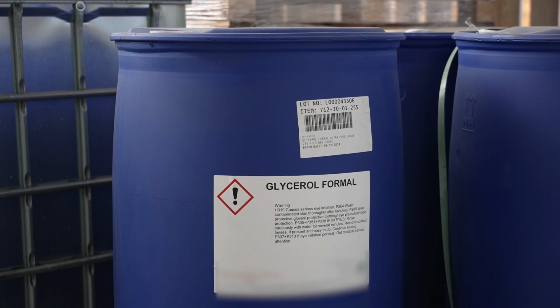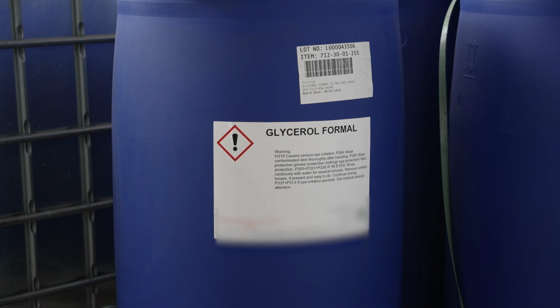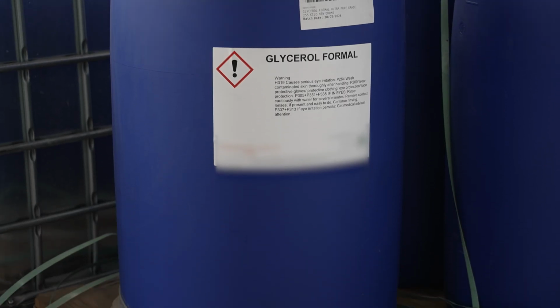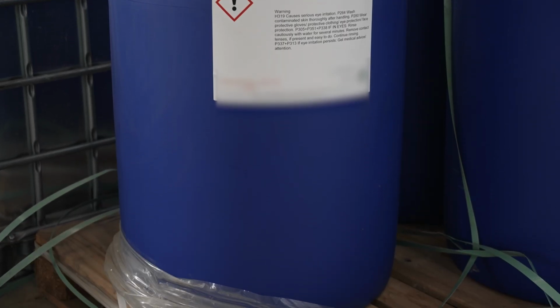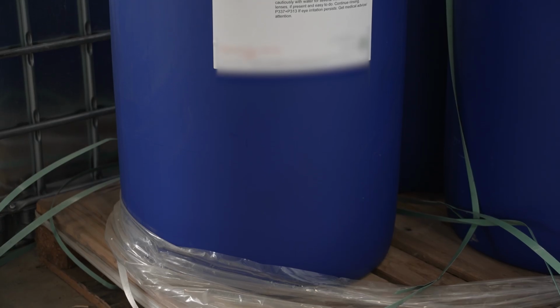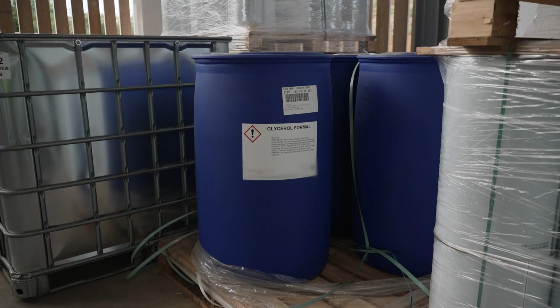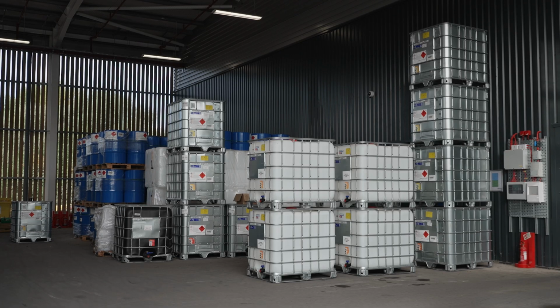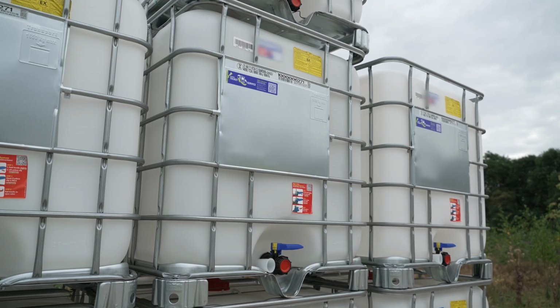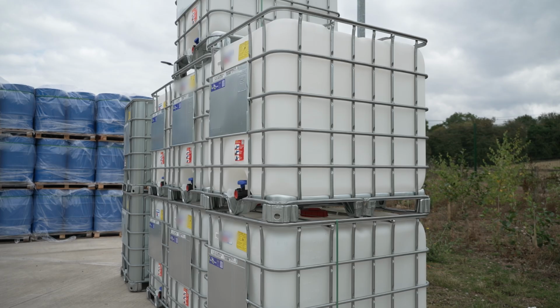Generally, it is recommended that plastic IBCs and drums should not be used for liquids with low flash points, as the plastic surfaces themselves can become charged by brushing against them and any charge buildup in the liquid cannot be removed. Some plastic containers have a special provision for earthing, and the operator must ensure that the container is robust and meets the manufacturer's specifications.